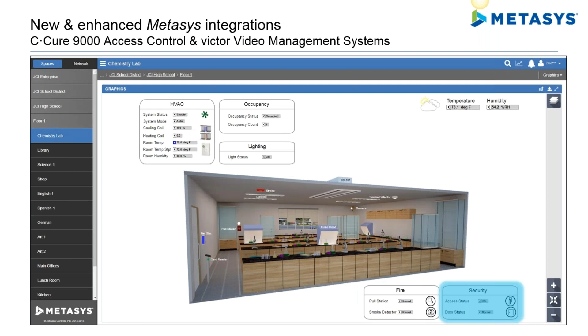For example, you can incorporate a badging event into an overall building-wide system occupancy strategy, such that when an occupant leaves the building for the day and swipes his badge out and exits the building, not only is that exit event recorded in the security system, but it's shared with Metasys so that the person's office temperature controls could be set back to an energy-saving, unoccupied temperature set point. The office lights that were providing light in his area could be turned off to save energy. Those are the types of operational features that can be accomplished by integrating access control with HVAC.